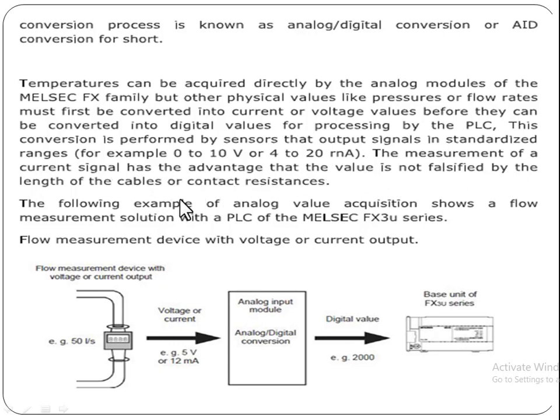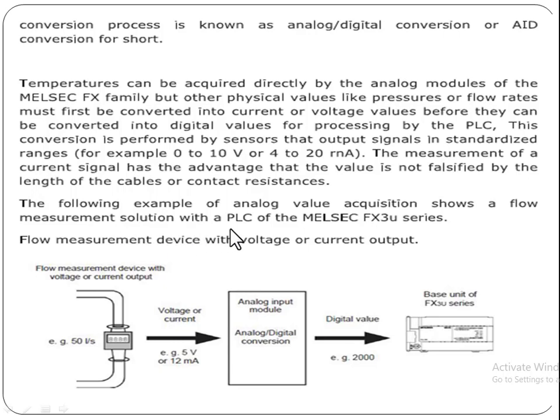The measurement of a current signal has the advantage that the value is not falsified by the length of the cables or contact resistances. This means the current signal is not affected by cable length.